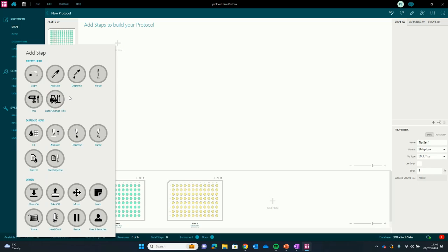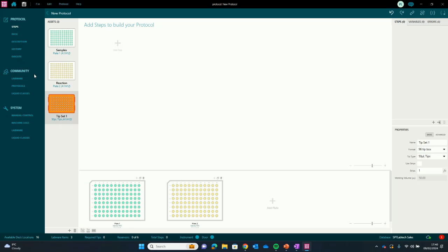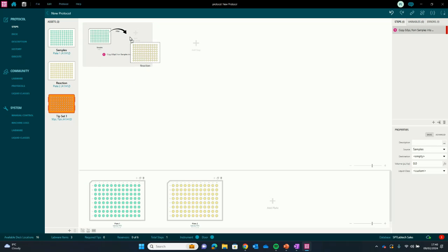And here I've got pipetting steps, dispensing steps for our non-contact dispenser, and then other things like moving plates, shaking, pauses, etc. So I'm going to use this copy step up here, which is in pipetting, and I'm going to go from samples to reaction. Now that I've got this highlighted, I can also set the volume that I want to actually pipette.